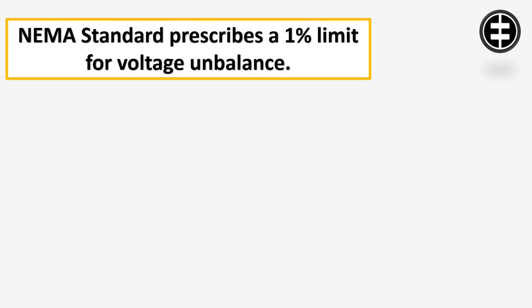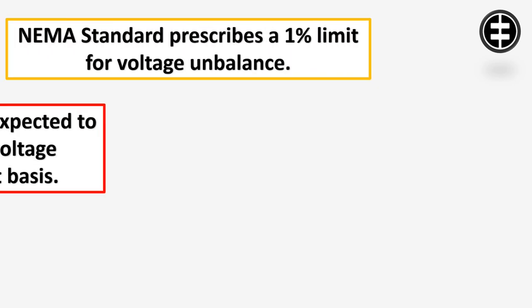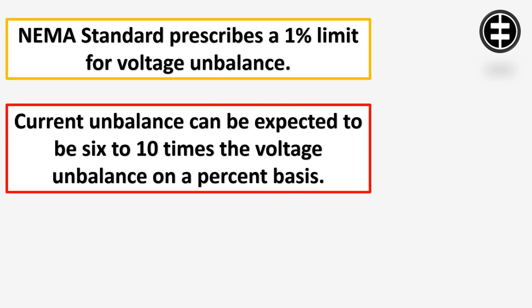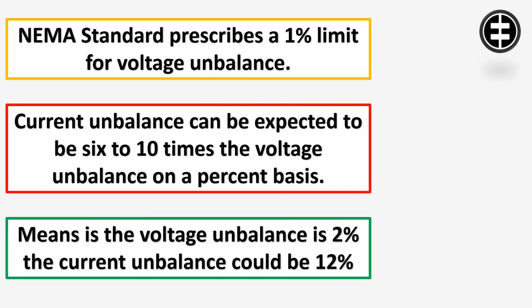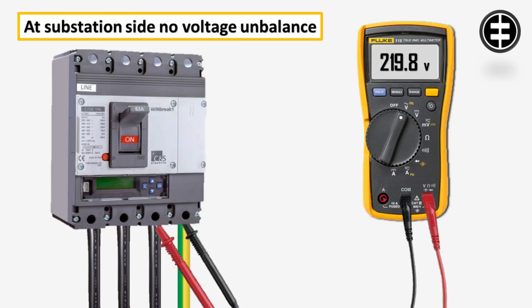NEMA standard prescribes a 1% limit for voltage unbalance. Current unbalance can be expected to be 6 to 10 times the voltage unbalance on a percent basis. To correct the voltage unbalance, you need to measure the three-phase voltage at the motor side and the main substation side.